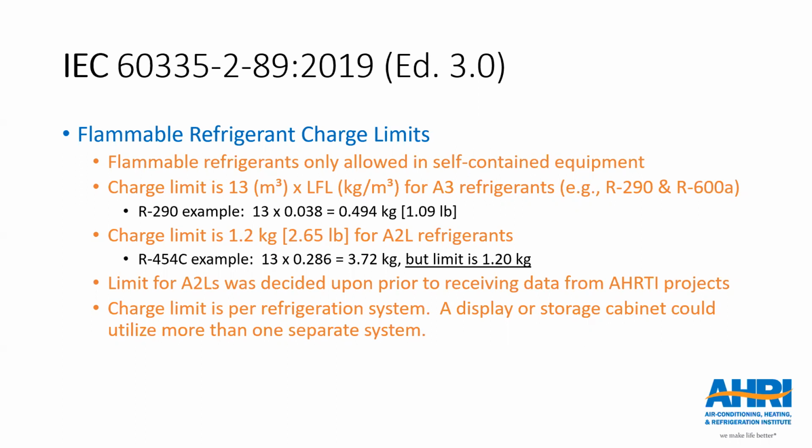The charge limit for flammables is 13 times the LFL, or the lower flammability limit of the refrigerant, or 1.2 kilograms, whichever is less. As you can see for R290, which has an LFL of 0.038, this is approximately 500 grams, a little bit less than that, or 1.1 pounds. Due to their higher LFL values, effectively the 1.2 kilogram cap only applies to A2L refrigerants.